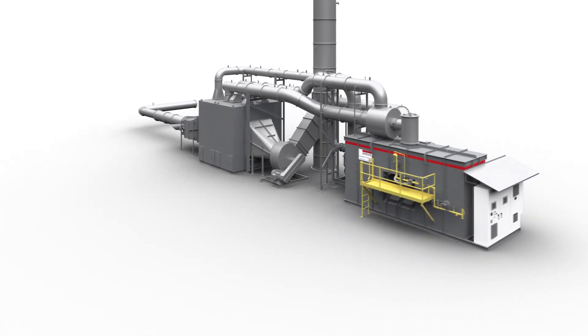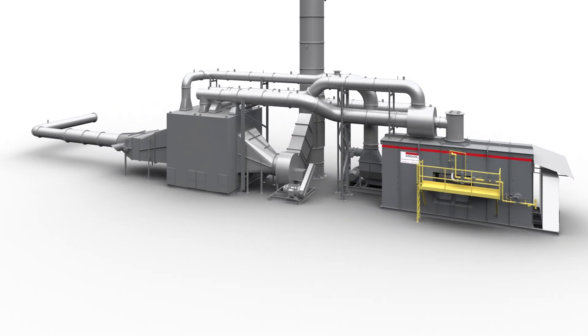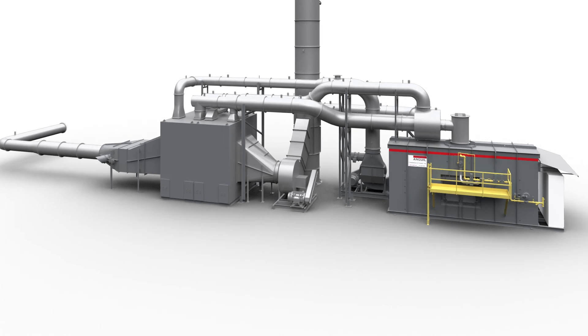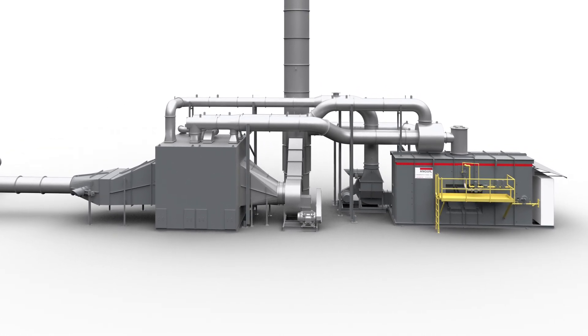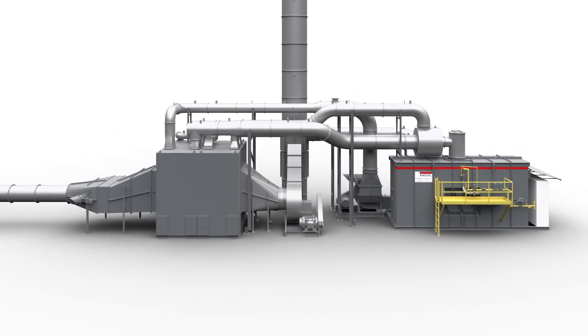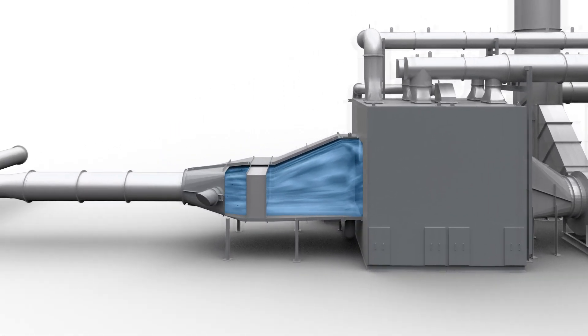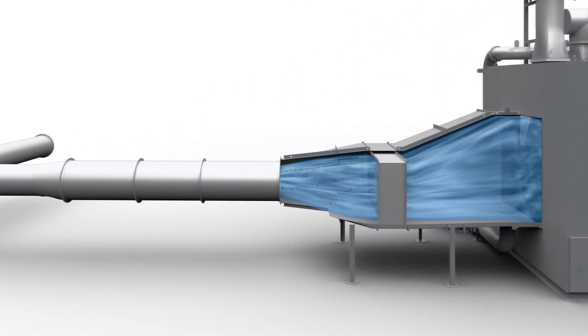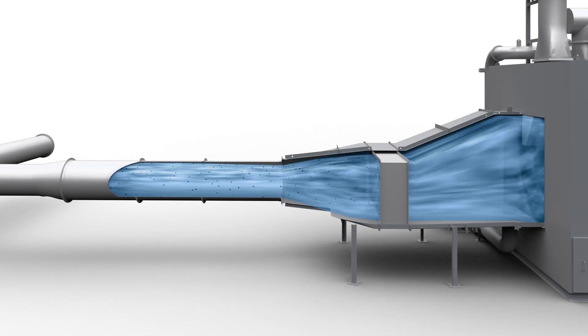When coupled with a concentrator, an oxidizer will operate with very little supplemental energy. At high concentrations, it even has sufficient free energy to provide desorption heat for the concentrator without consuming any auxiliary fuel. Concentrators and the corresponding oxidizer have the unique ability to treat industrial emission sources with high-volume, low-concentration characteristics.